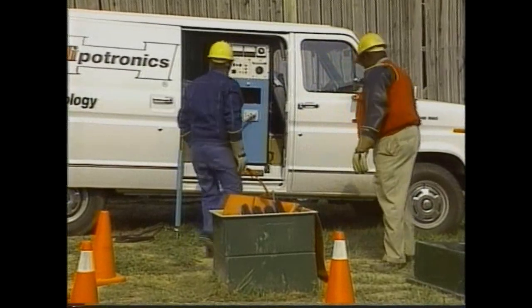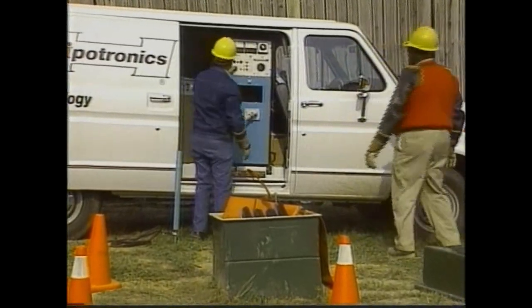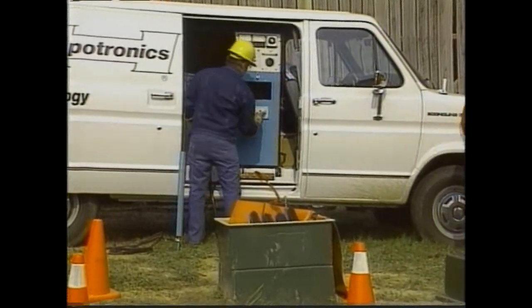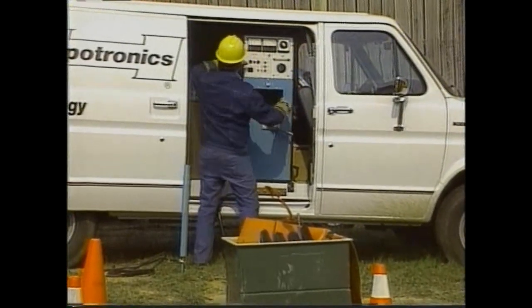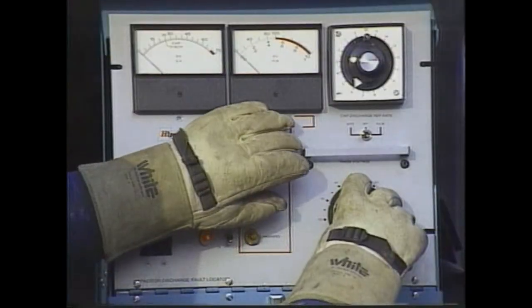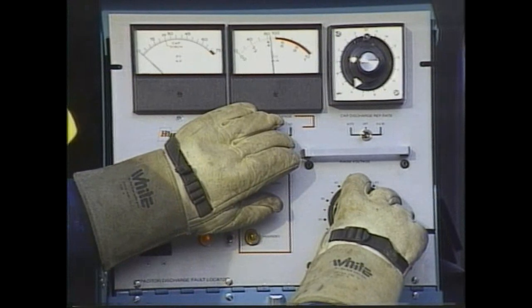We turn the thumper on and adjust for a low current meter reading in the burn mode. This tells us if we can start our thump. It appears from the meter reading that we can thump this fault. We set the thumper in the thump mode.